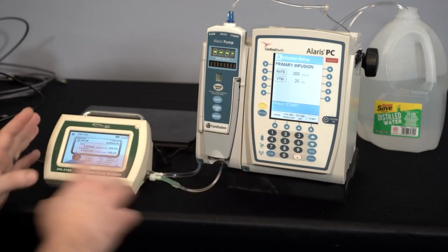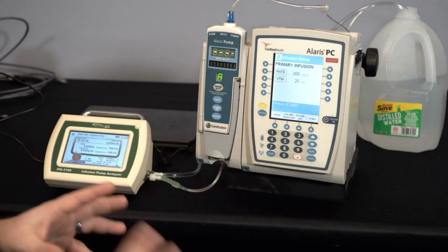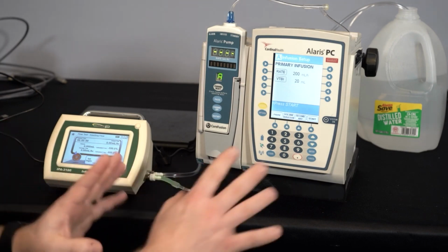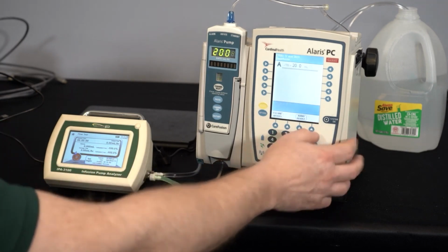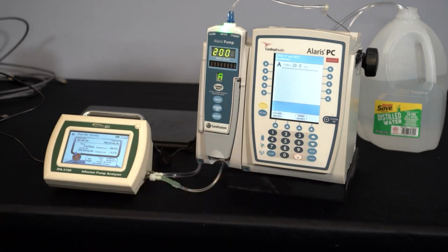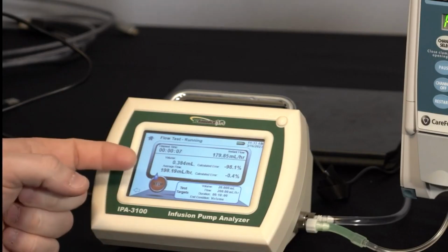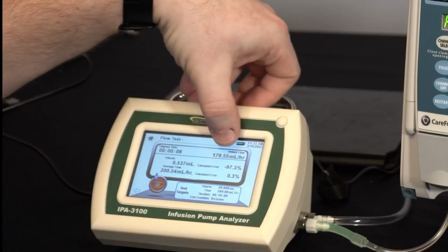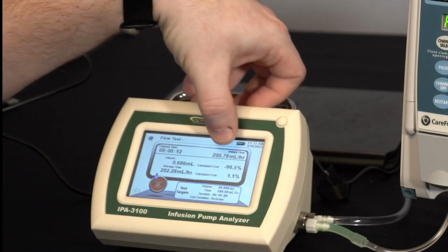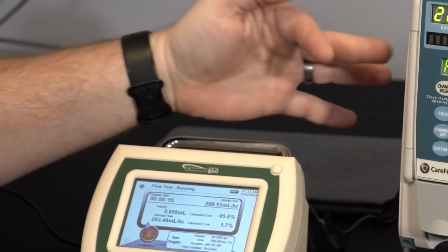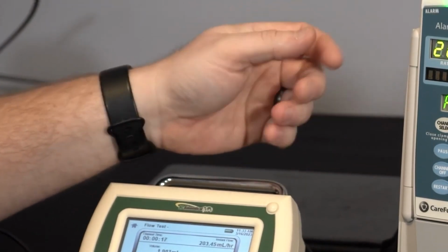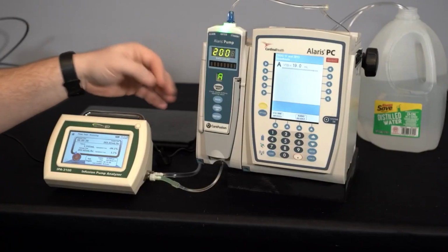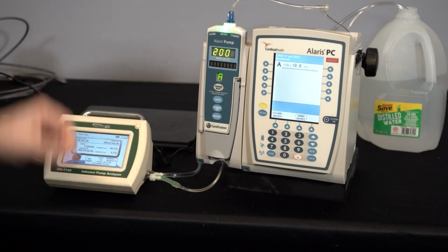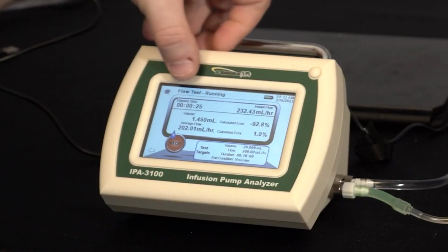So this allows me to do whatever configuration I need to on the pump. I don't have to worry about pushing this button and pushing that button at exactly the same time. The auto mode just waits, and as soon as it detects flow, it starts measuring. So I started the flow on the pump, and then I've got measurements on the screen. So it's going to show me the average flow. Up at the top is the instantaneous flow. And what we'll see, this number is going to bounce around a little bit because, you know, inside the pump it has fingers that it's using, and sometimes it moves faster and it has to cycle through those fingers. So that instantaneous flow is going to be all over the place.